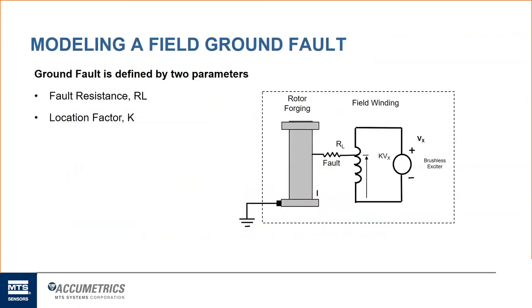So here's an example, basically modeling what a field ground fault may look like. First we have to define an analytical model for a ground fault. It's defined as some value, RL, some resistance, and some location on the field windings on the rotor. What it is just basically looking for is the potential difference of a fault location relative to the negative side of the field windings and rotor ground itself. Zero is at the negative side, and 1 or 100% would be at the positive side of the field windings. We provide what's called location factor, K, and we'll go into that in more detail as we cover the process of how Accumetrics measures for a ground fault.